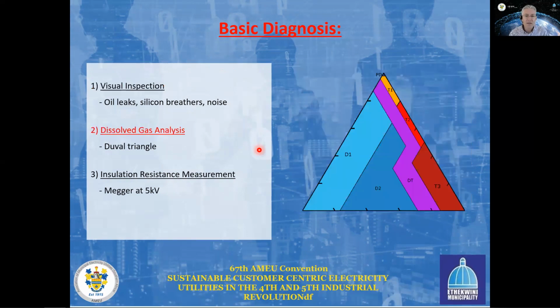Secondly, we've got the dissolved gas analysis, which means we take an oil sample from this transformer on a regular basis, and we plot the results from that oil analysis in the Duval triangle shown on the right-hand side here, where we plot the methane content, the ethylene content, and the acetylene content against each other. And this would indicate to us if there have been any high energy thermal faults inside the transformer, if our oil sample would fall into one of the T1, T2, or T3 areas on the right-hand side, those red areas shown in this diagram that you see here. Or if it's more on the left-hand side of the diagram, it would tell us that there have been discharges of low energy inside that transformer. This is a very good diagnosis technique on a power transformer on an ongoing basis. It should be done on a transformer on a regular basis.